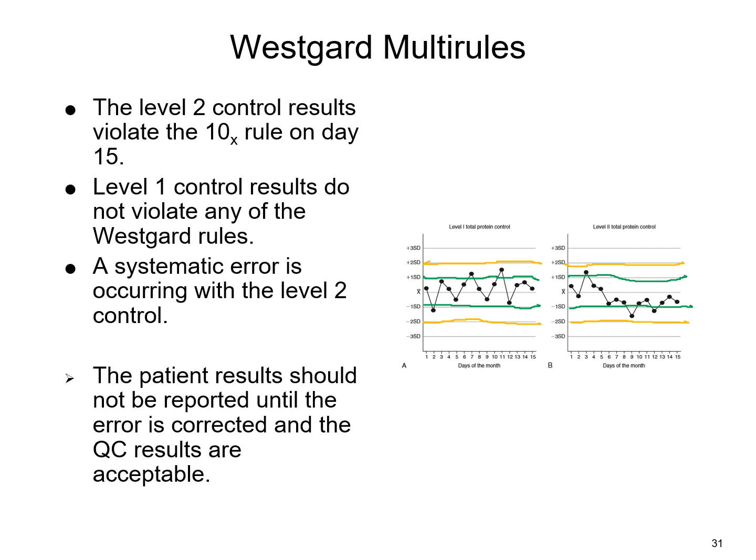Do we have 4 consecutive values outside of 1 standard deviation? So if we look at this within each slot or across runs, we still don't really have, for level 1, nothing in those 4 days or the 2 days that violates the 1S. Within the 4 days, we do have that 1S, but it's not consecutive violating. So that rule, the 4-1S rule, is not violated.